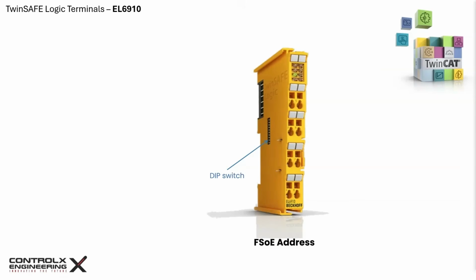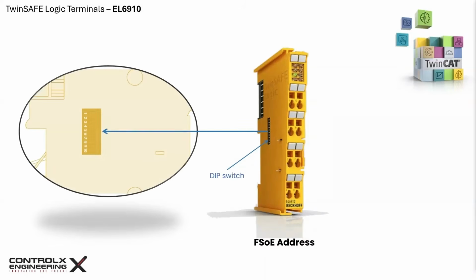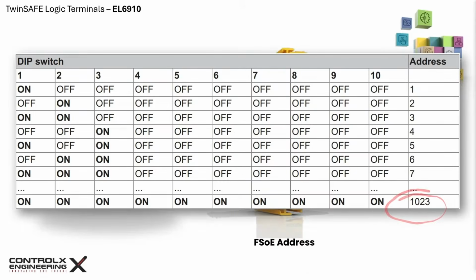We need absolute certainty. Depending on the model, you will see either one dip switch block or 2 dip switch blocks, giving you enough combinations to assign a unique address to each safety device on the EtherCAT network. Devices like the EL6910 and EL2904 have single dip switch blocks with 10 switches labeled from 1 to 10, which gives us addresses from 1 to 1023 as shown in this table. Each FSoE address has to be unique and may only be used once within a network. Also note that 0 is not a valid FSoE address.